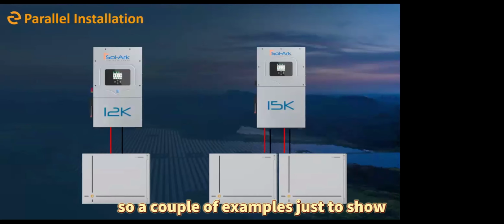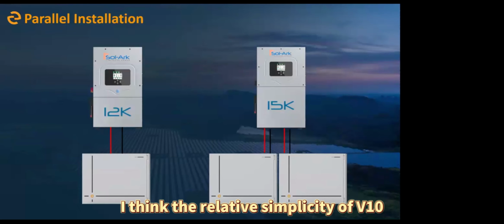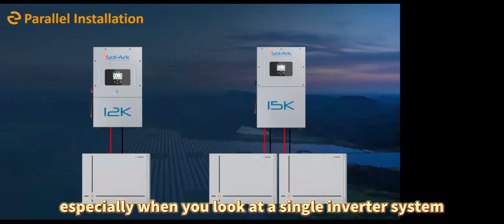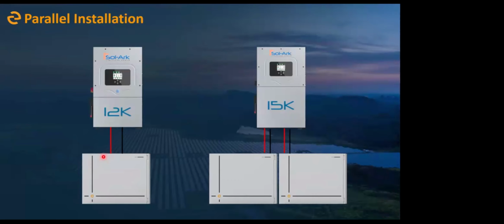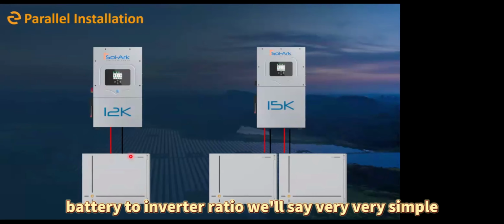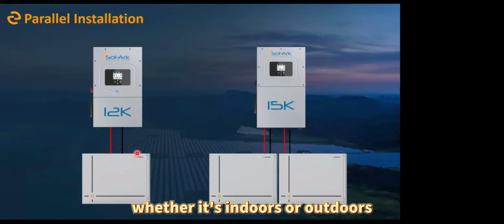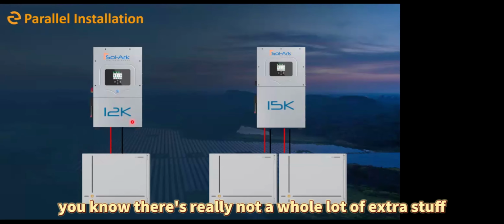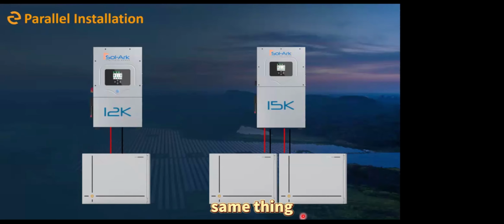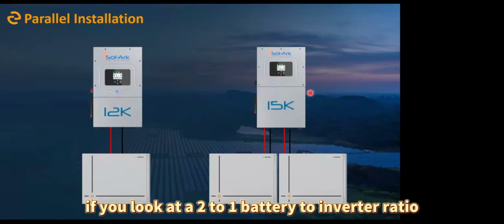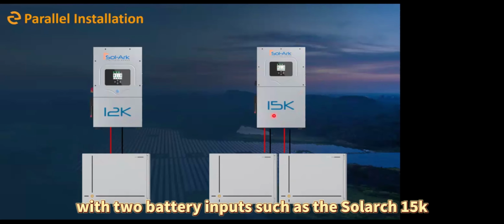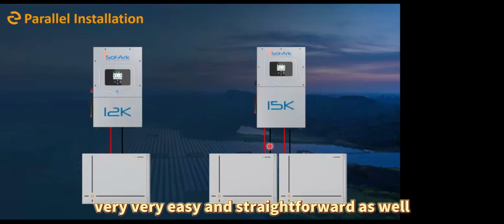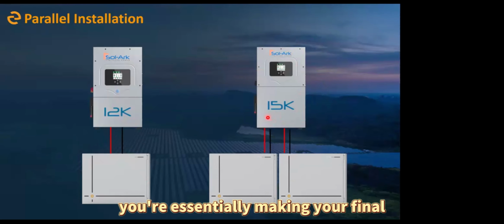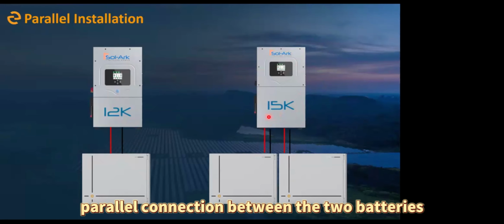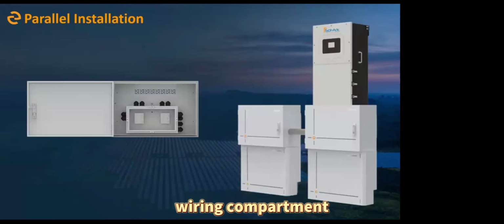So a couple of examples just to show the relative simplicity of V10, especially when you look at a single inverter system - a 1-to-1 battery to inverter ratio, very, very simple. Whether it's indoors or outdoors, there's really not a whole lot of extra stuff you're going to need to facilitate that. Same thing if you look at a 2-to-1 battery to inverter ratio, especially if we're using an inverter with 2 battery inputs, such as the Sol-Ark 15K. Very, very easy and straightforward as well. You're essentially making your final parallel connection between the 2 batteries right there in the inverter wiring compartment.